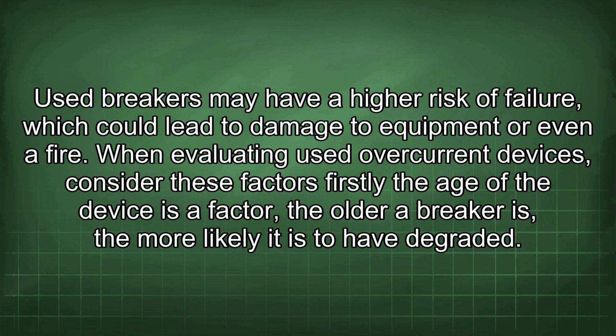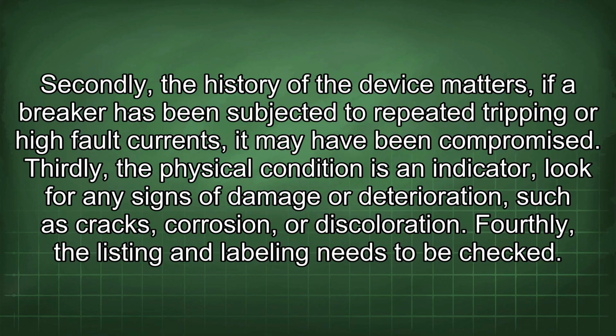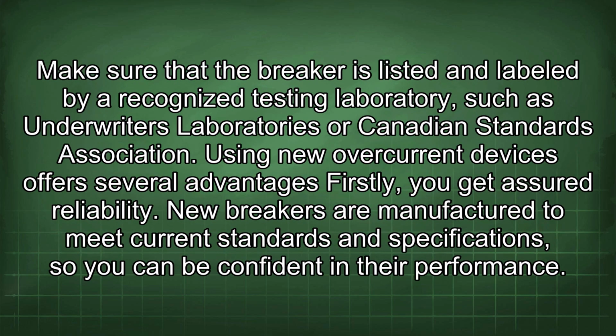Firstly, the age of the device is a factor. The older a breaker is, the more likely it is to have degraded. Secondly, the history of the device matters. If a breaker has been subjected to repeated tripping or high fault currents, it may have been compromised. Thirdly, the physical condition is an indicator. Look for any signs of damage or deterioration, such as cracks, corrosion, or discoloration. Fourthly, the listing and labeling needs to be checked. Make sure that the breaker is listed and labeled by a recognized testing laboratory, such as Underwriters Laboratories or Canadian Standards Association.